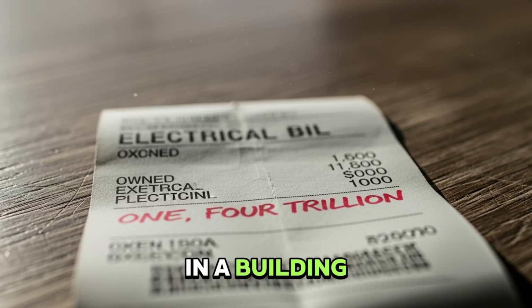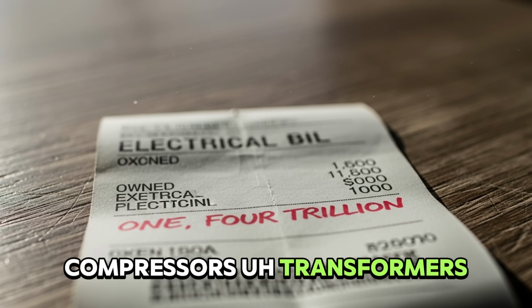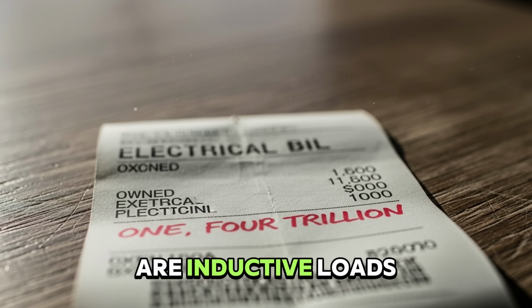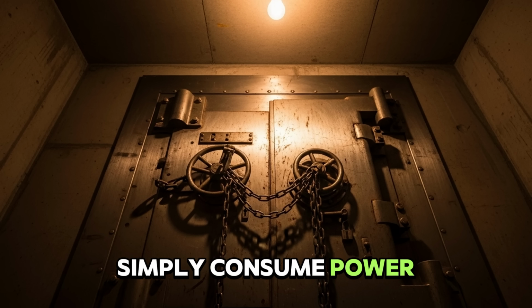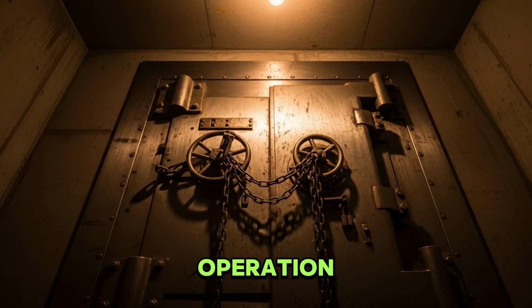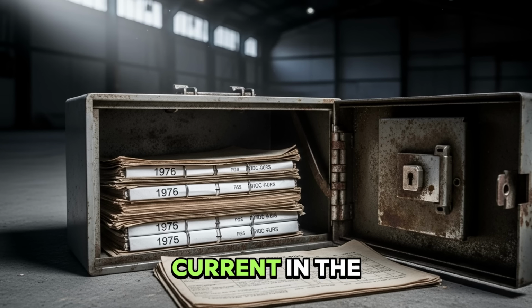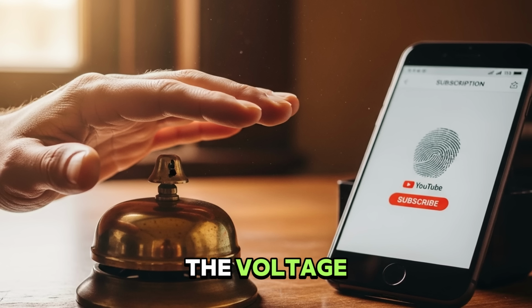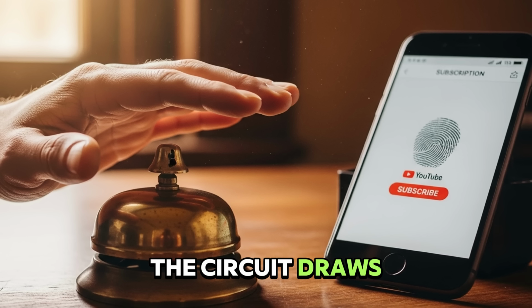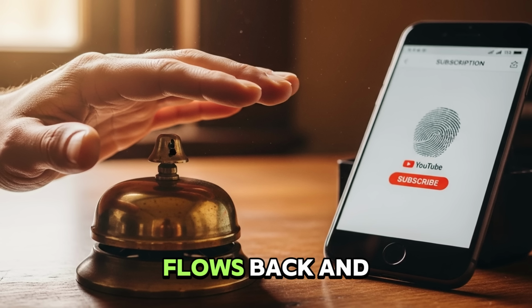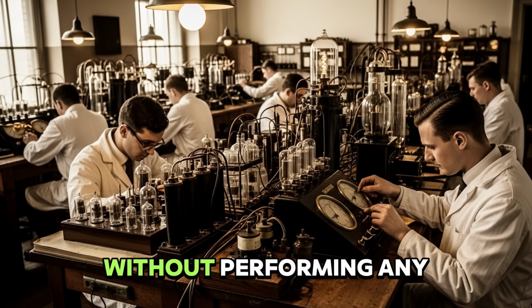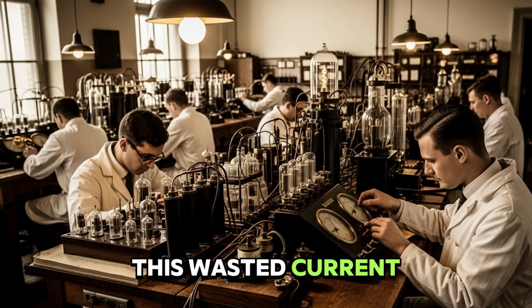Most electrical loads in a building, motors, compressors, transformers, fluorescent lighting ballasts, are inductive loads. They do not simply consume power. They create a magnetic field as part of their operation, and that magnetic field causes the electrical current in the circuit to fall out of phase with the voltage. When current and voltage are out of phase, the circuit draws more current than it actually uses. The excess current flows back and forth between the load and the power source without performing any useful work. This wasted current is called reactive power.